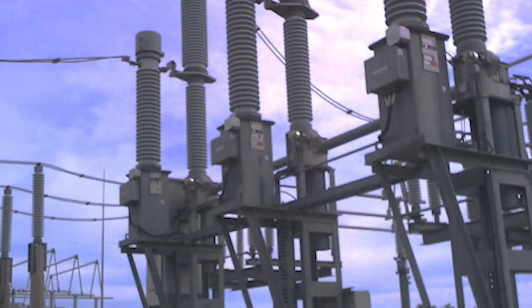This is a picture of a 250,000 volt breaker. We are standing back 7 to 10 meters looking up at the breaker in full spectrum. Photographing each piece of equipment in full spectrum helps us to identify and reference the equipment when we are authoring reports, and it provides a historical reference photo for future reports. It helps in tracking the health of the equipment. FLIR's thermography software provides this functionality, saving the time required to take a photograph with another camera.